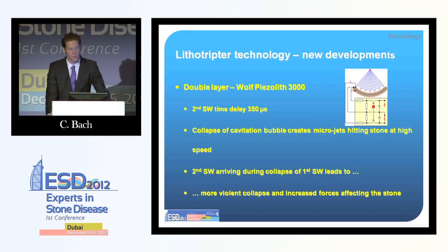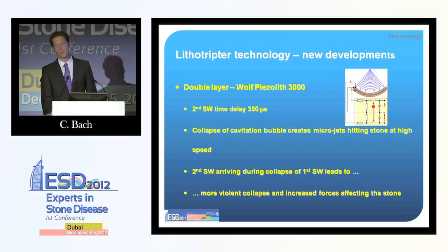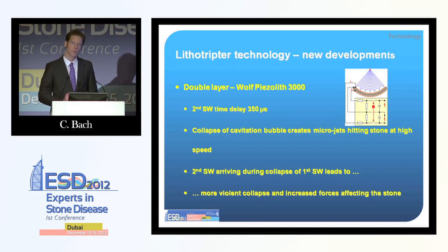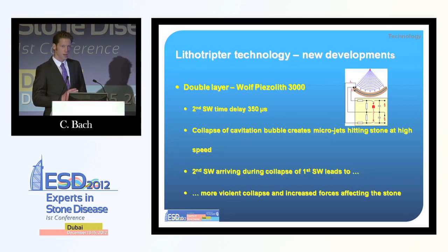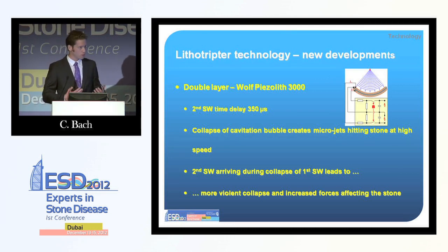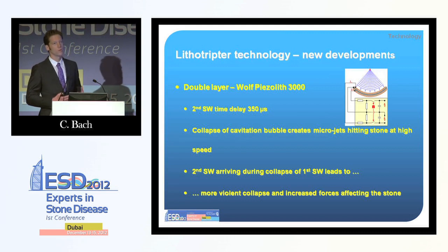Another interesting technique is the Wolf Piezolith 3000. As the name says, it's a piezoelectric membrane generating the shock waves. In this system you have two piezoelectric membranes able to produce two shock waves focused on one point, which can be fired either simultaneously or with a short delay — meaning the second shock wave is driven onto the cavitation bubbles generated by the first, increasing their impact on the stone. However, in reality, stone-free rates are not better with this machine than with other electromagnetic machines; they rather seem to be a little bit lower.